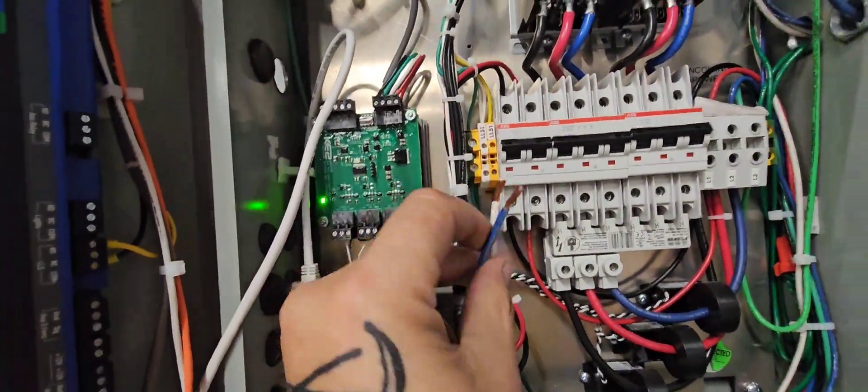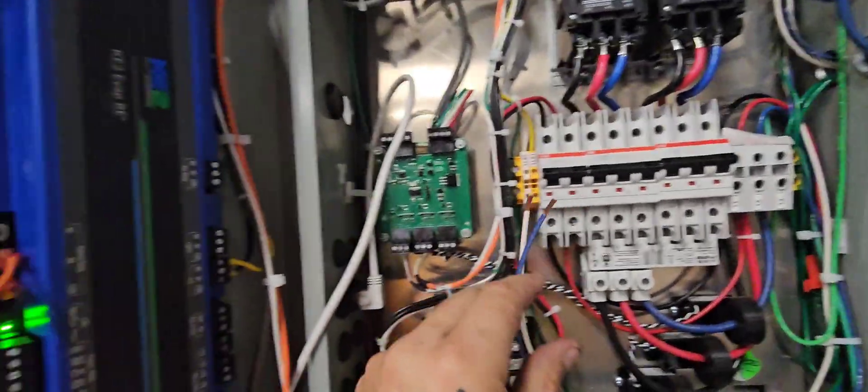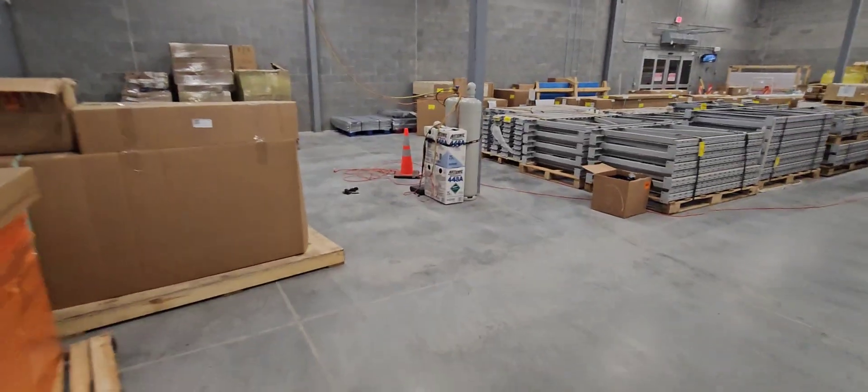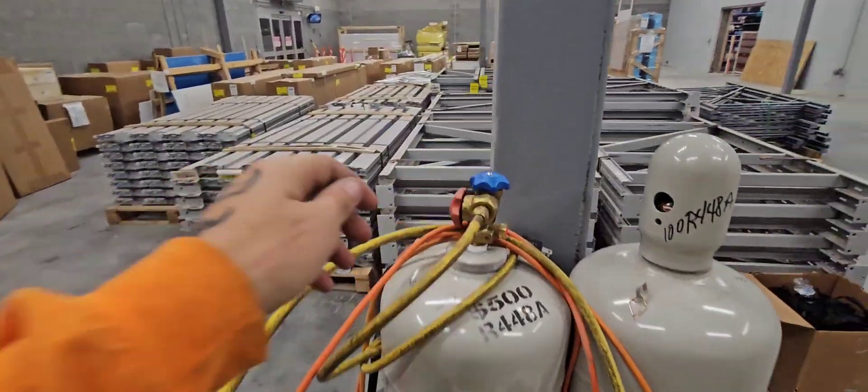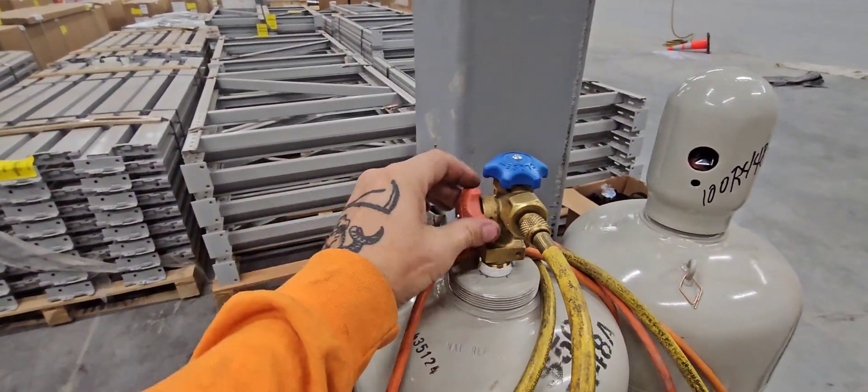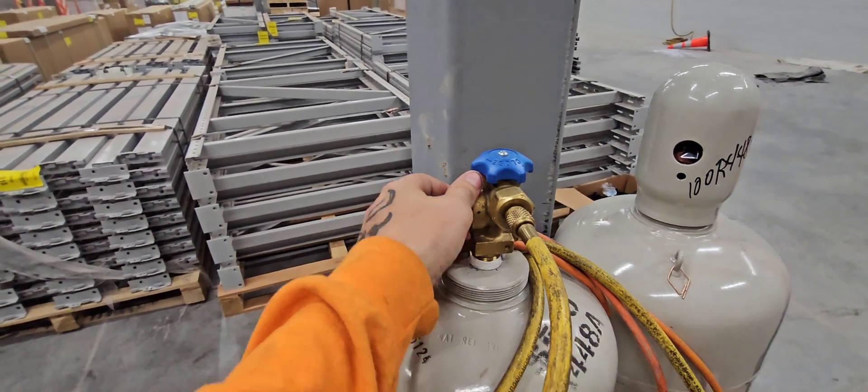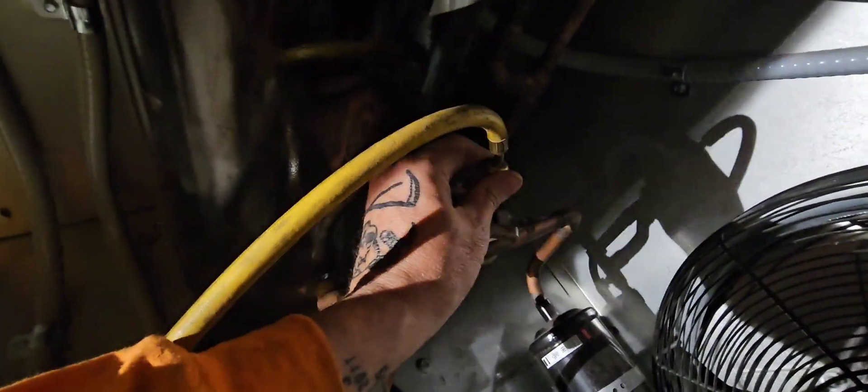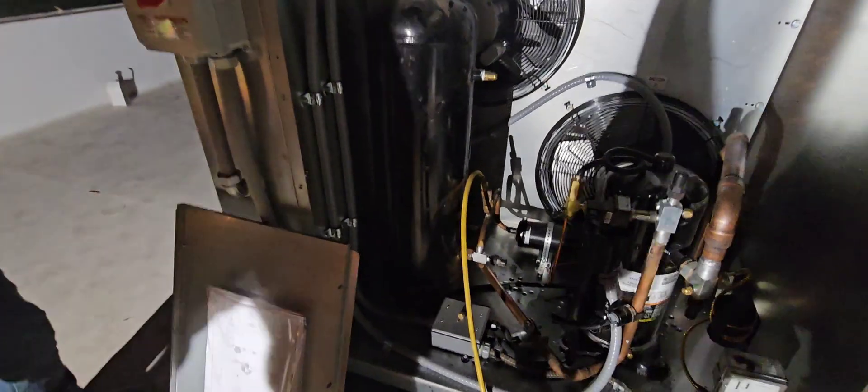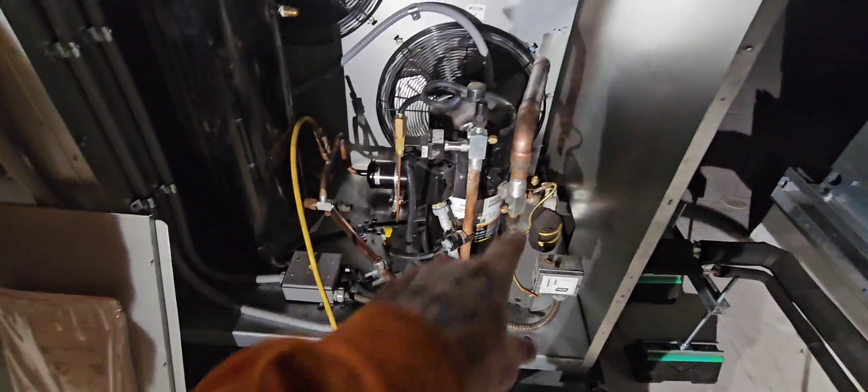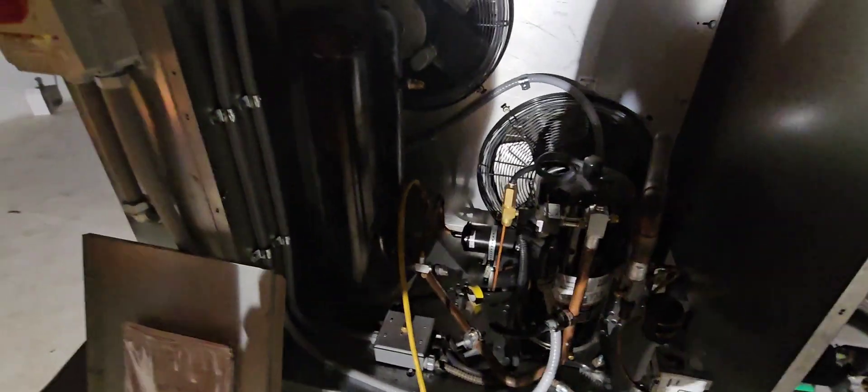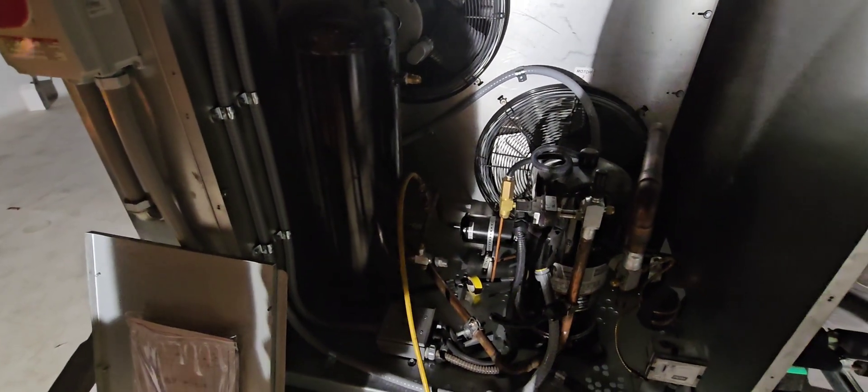We got power to that board. I've got the solenoid disconnected so our solenoid on top of the box is de-energized. So now we are good to start charging this thing up. I have all the hoses and everything upstairs closed so I'm just going to open this right here and then go up on the roof, purge it at the roof and start dumping it in. We got the refrigerant turned on downstairs, so purge it up here. And now we're just going to let it rip until it doesn't and then we're going to be occasionally checking that receiver. I doubt we'll put the full charge in before we have to go in the suction. We're just going to let it run and then see how much it takes.